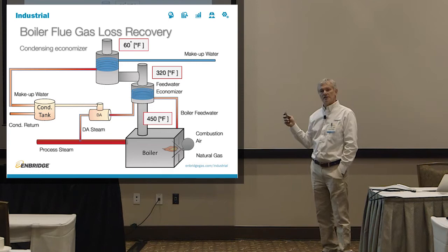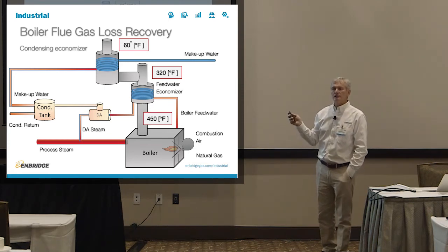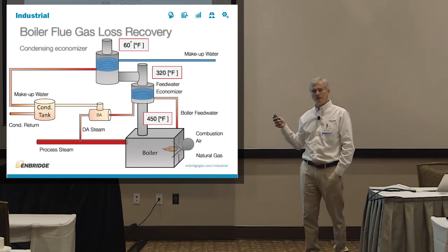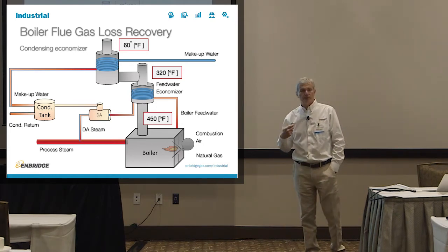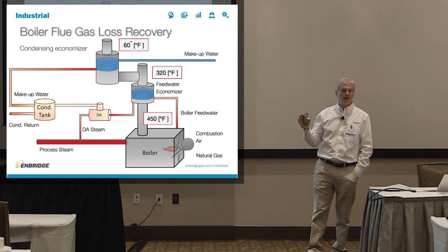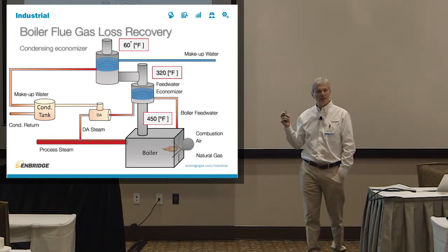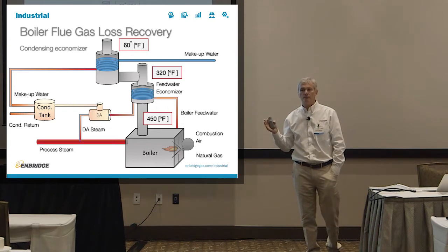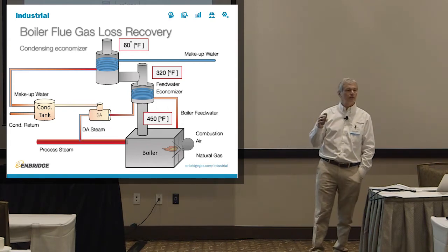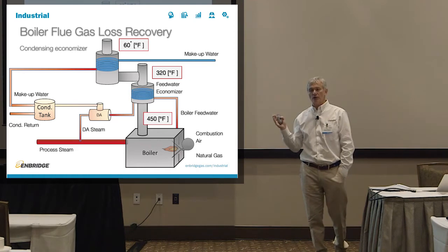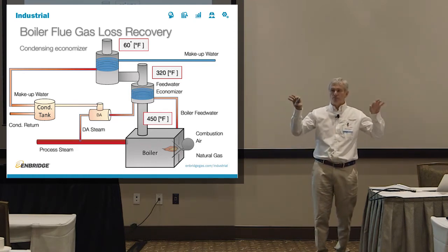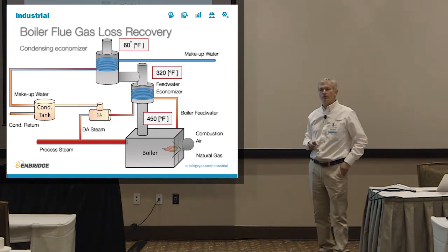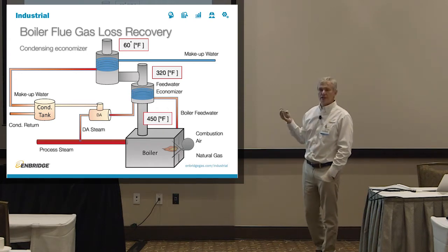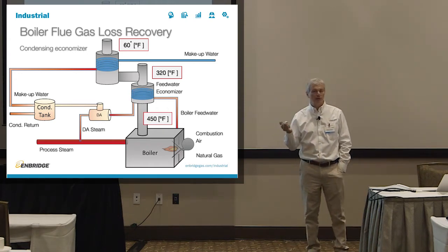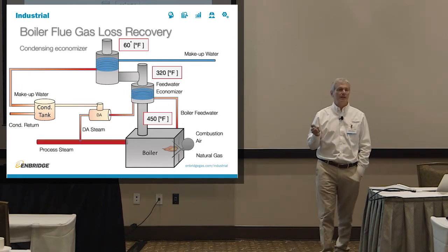Now you can get the temperatures down theoretically to 60 degrees F coming out of the condensing economizer. My personal preference is I would leave that at about 90 to 110 degrees F, only because at 60 degrees F exit temperature, you'll create your own weather system. If you've ever stood underneath a flue gas stack coming out that cold, you will have nice little moisture coming out of it, showering you. So I would not go that low, but even if you go down to 100 degrees F, you have recovered an amazing amount of energy.